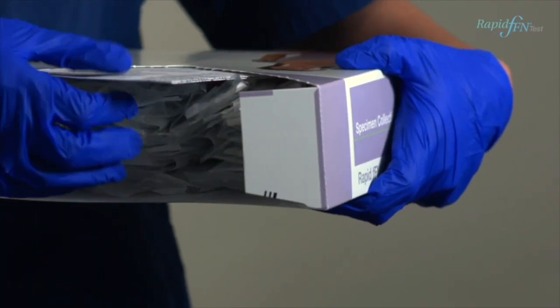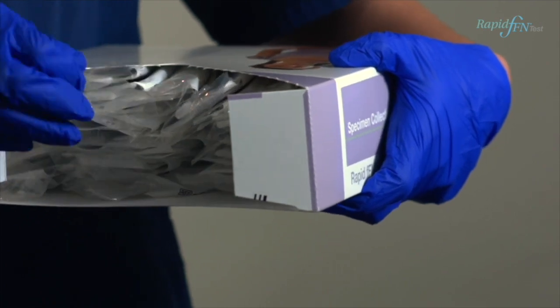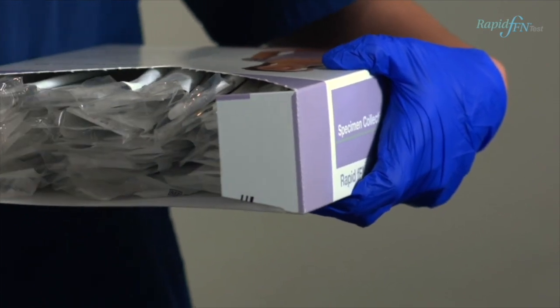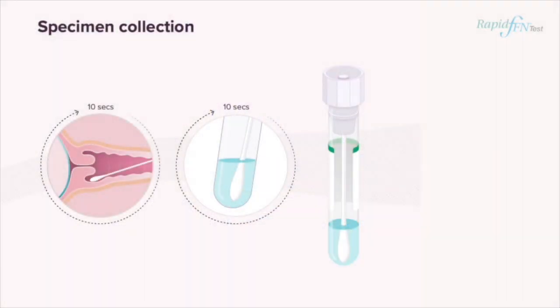Ensure you only use the specimen collection kit provided by Hologic for the purpose of a fetal fibronectin test. During speculum examination, lightly rotate the swab across the posterior fornix of the vagina for 10 seconds to absorb cervicovaginal secretions.